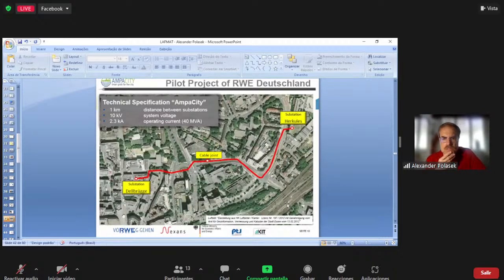And this is the longest pilot cable existent in the world, the so-called AmpaCity project in Germany. This is a 1 kilometer cable transmitting at 10 kilovolts, above 2 kiloamps, and it substitutes, if you had a conventional cable here, you would need 100 kilovolts. It means by using such a cable, you can save one substation. And this can justify the use of superconductor.